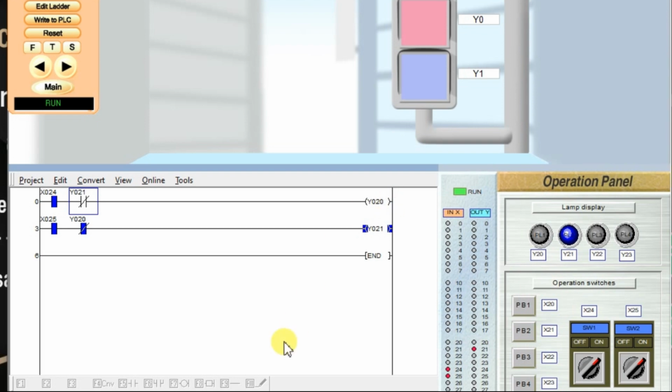This is the interlocking. Okay, this is a simple interlocking concept with first input priority. Remember that we have many types of interlocks available. This is for first input. If I give the first input for forward direction, then the reverse direction is disabled. Similarly, if I give first input for reverse direction, then the next instruction will be disabled, that is forward direction. This is interlocking with first input. Whatever input is given by the operator first, that will be taken.